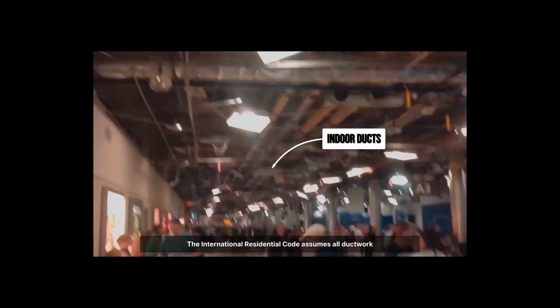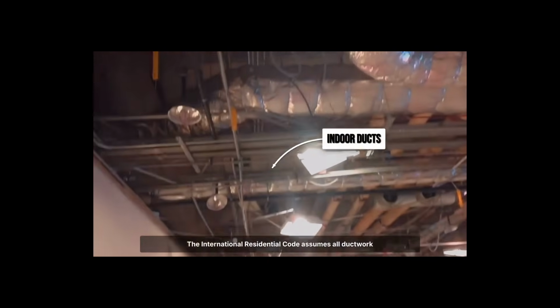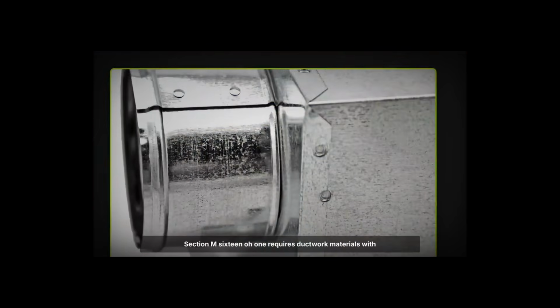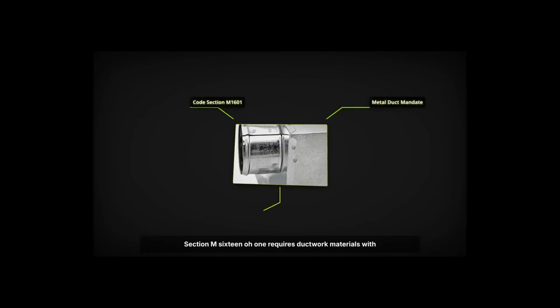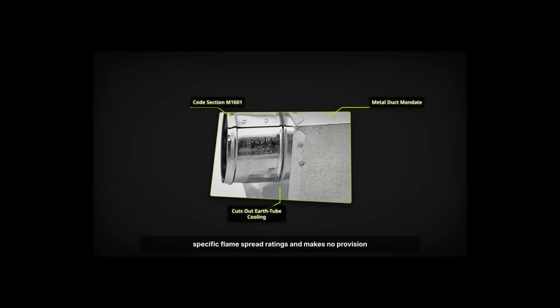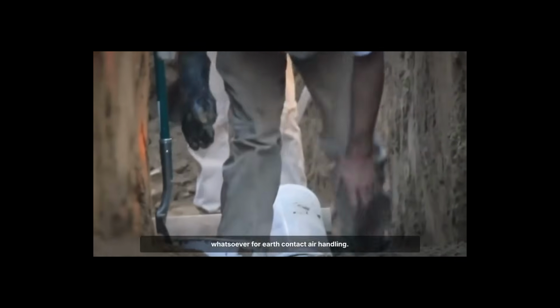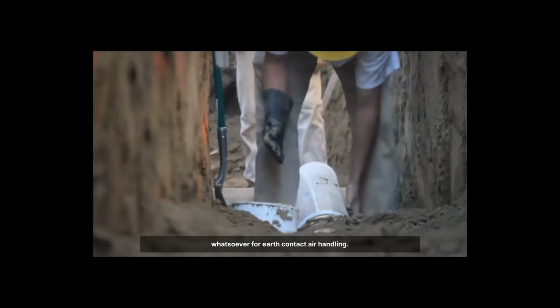The International Residential Code assumes all ductwork exists inside buildings. Section M1601 requires ductwork materials with specific flame spread ratings and makes no provision whatsoever for earth contact air handling.